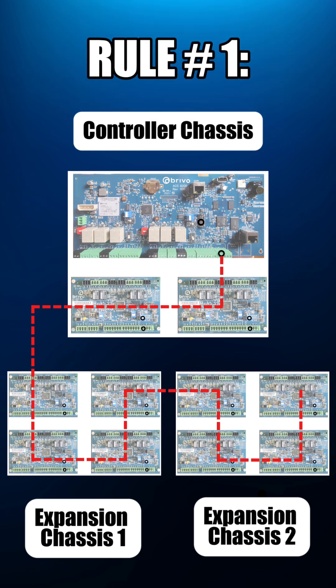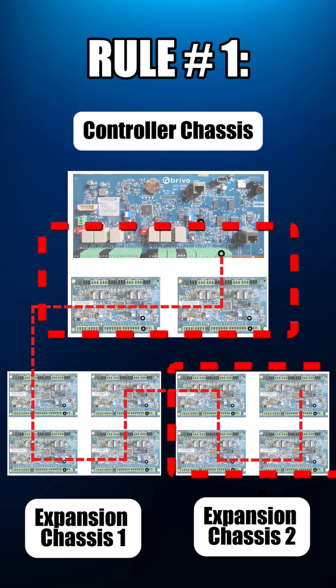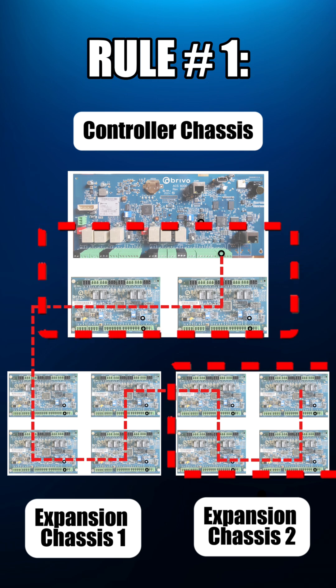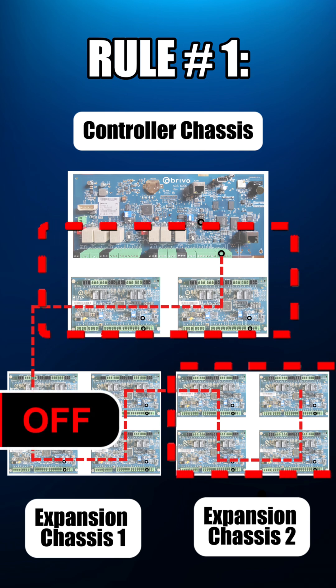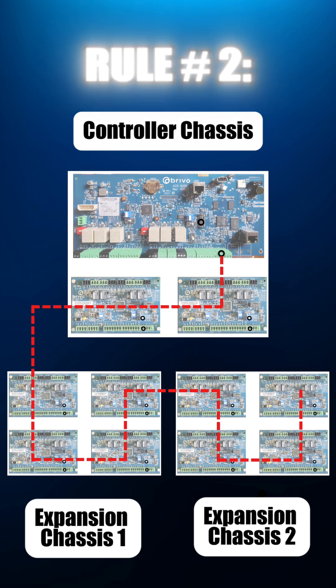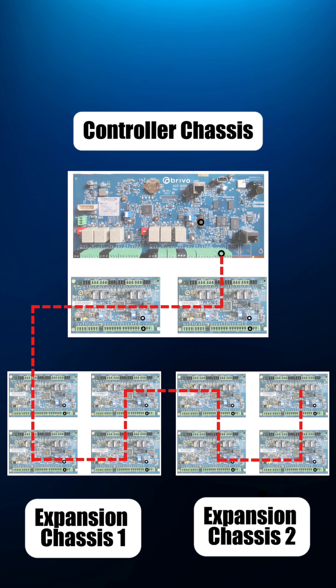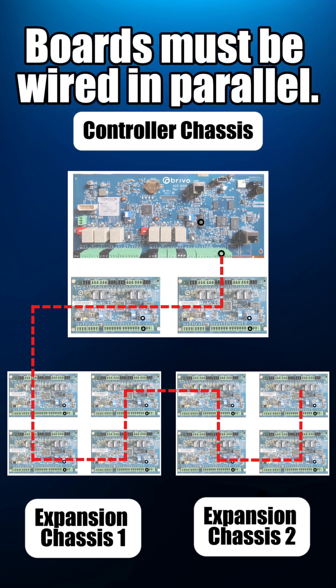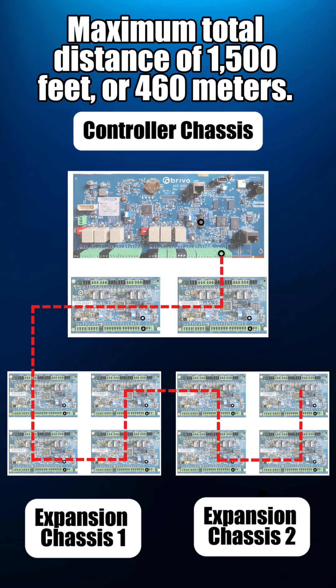Rule 1: Only enable termination switches at the first and last panels. All switches in the middle must stay off. Rule 2: Boards must be wired in parallel, with a maximum total distance of 1,500 feet or 460 meters.